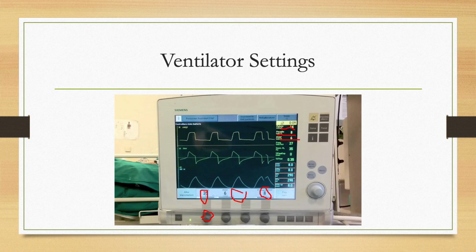The next value is, they're kind of hard to see, but one is the oxygen delivery. That's a backup mechanism that basically just verifies that you're getting the oxygen content that is set. The next is inhaled and exhaled minute ventilations. So minute ventilation is respiratory rate multiplied by tidal volume.